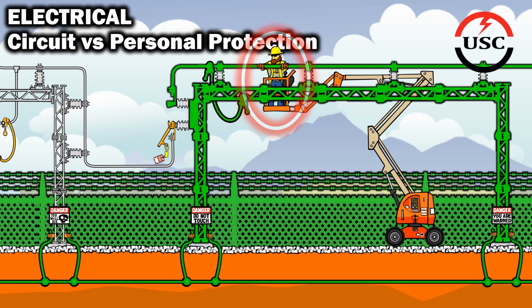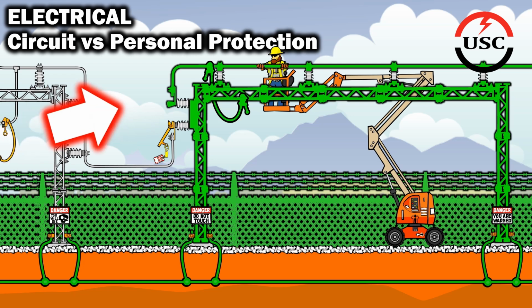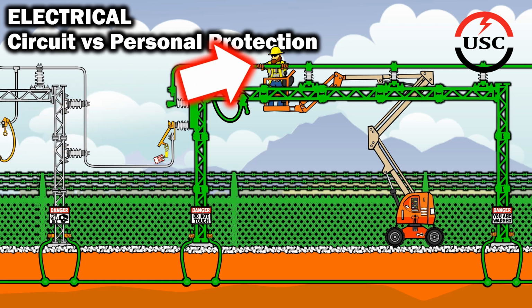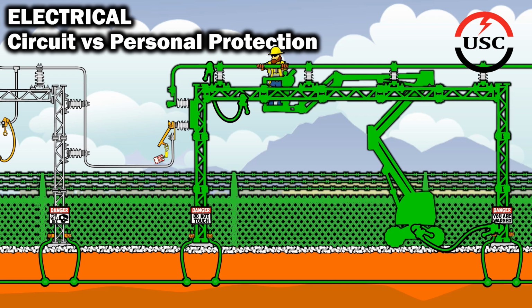Is the worker protected? The man lift is not bonded to an effective ground, therefore it is not at the same potential as the buswork. As a result, if the worker contacts the buswork without dielectric protection, then he is the meat fuse. The structural steel is bonded to an effective ground, which is the substation ground grid. Bonding the man lift to the structural steel then grounds the man lift. Theoretically, the worker has now eliminated 2 points of electrical contact, therefore he is safe.